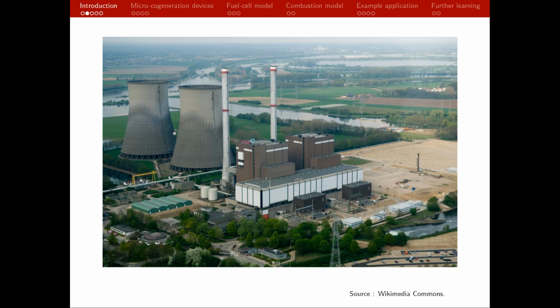So the goal of the cycle design is to convert as much of the thermal energy as possible to electricity. However, the laws of thermodynamics being what they are, we know we can't convert 100% of that thermal energy to electrical power—there will be some rejection of heat to the environment. In this case, cooling towers are used to reject heat, and anywhere between 45% and up to 70% of the thermal energy produced through combustion is rejected to the environment as waste heat. That is energy that's lost.